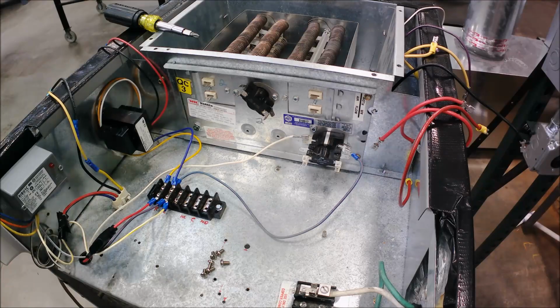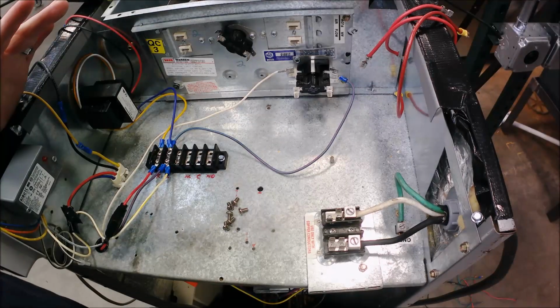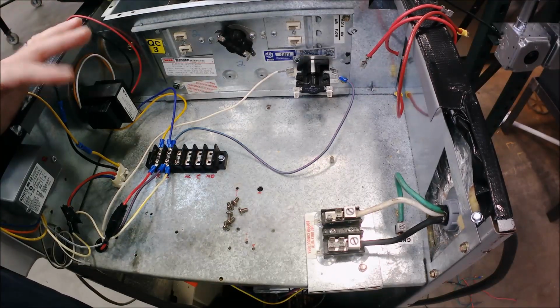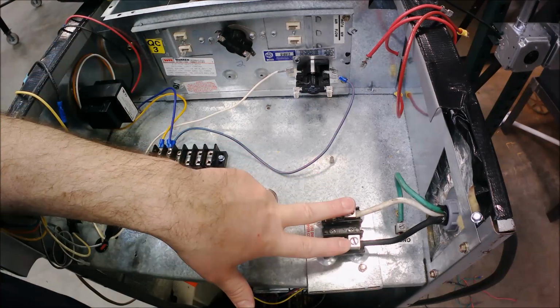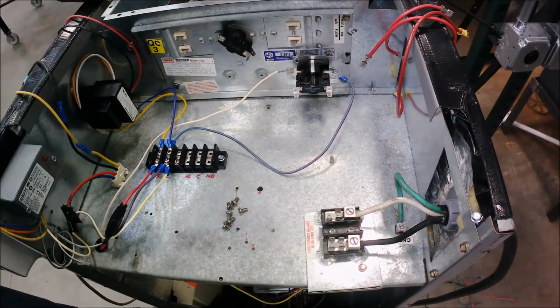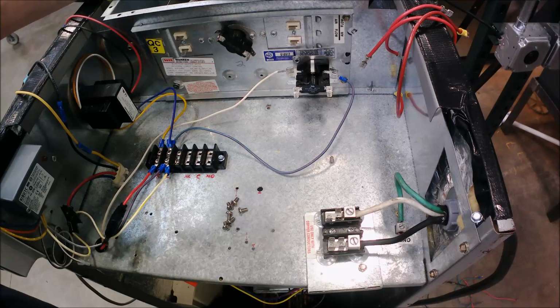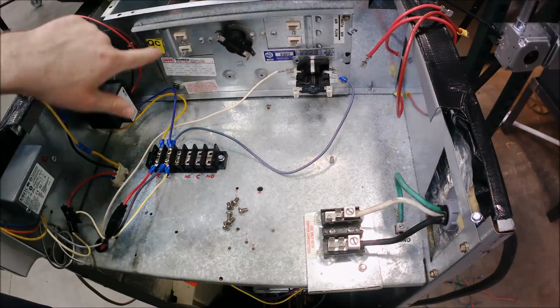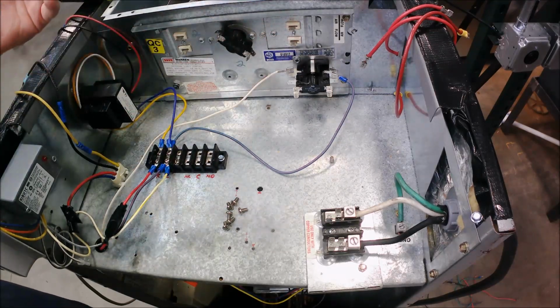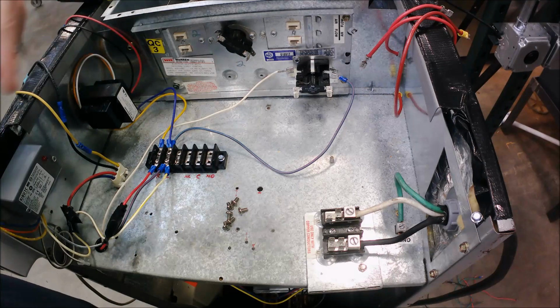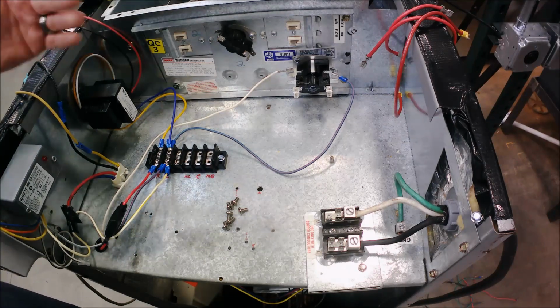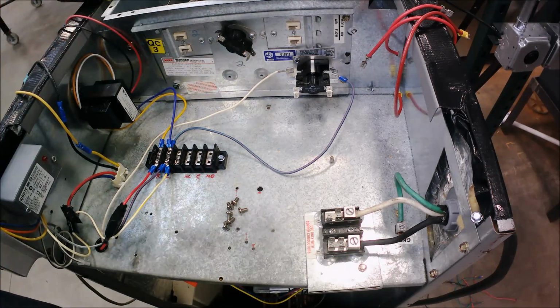Now we're going to move into the high voltage. Now that we have our low voltage done, what we're going to look at is the high voltage. Here's our terminal block. We have two heaters in here, one on the left and one on the right. So this is a heater and this is a heater. I'm only going to wire one of them. The principle will be the same for the second one. I just don't have enough amp draw on this particular circuit, or this particular outlet I'm going to plug into.